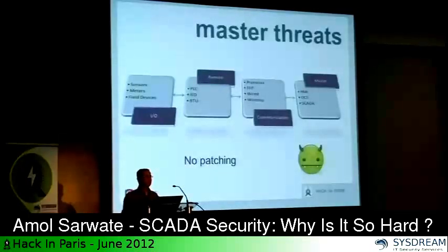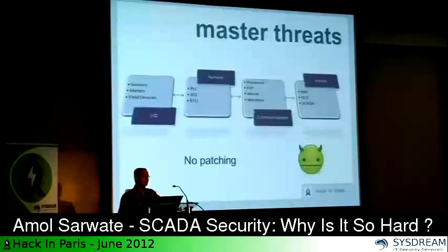Microsoft releases patches every Patch Tuesday, every month, at least a dozen patches. If I am a SCADA system administrator, what am I supposed to do? Am I supposed to just apply these patches blindly without knowing that this could cause something bad to my SCADA system? The SCADA vendors don't give any guidance to the SCADA administrators every Patch Tuesday that, okay, we have tested this patch, apply this patch, and your SCADA software would be fine. There is no guidance like that.